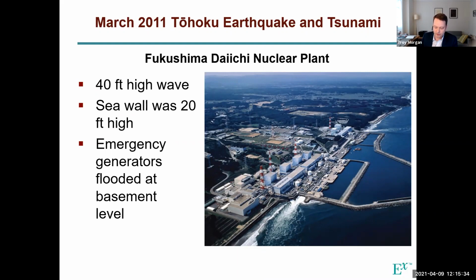And importantly, both for Fukushima Daiichi and for San Onofre, they're emergency diesel generators, which are meant to supply power to the station and to the critical parts of the station in case there's a loss of offsite power. So if the power grid goes down, the generators kick on and supply power to things like coolant pumps, which keep coolant circulating through the reactor core and prevent overheating until the core can be cooled off by inserting the control rods. But that takes time, and once you insert the control rods in the reactor core, it takes days for it to cool down enough to prevent an accident.